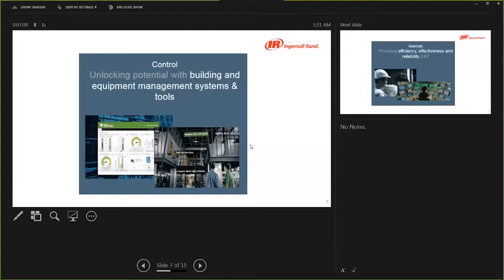They assure that the needs of every room are met for temperature, humidity, air quality, fresh air control at the highest possible system efficiency. They can now diagnose problems that are reducing efficiency, like clogged filters, scaled tubes, low refrigerant charges, equipment breakdowns before they become major concerns or before they consume a huge amount of energy. And they can tell you if the system is consuming more energy than expected for current ambient conditions and current expected building loads. And in that way, they can alert a facilities manager or a maintenance manager to where a problem might be before we consume a huge amount of energy.